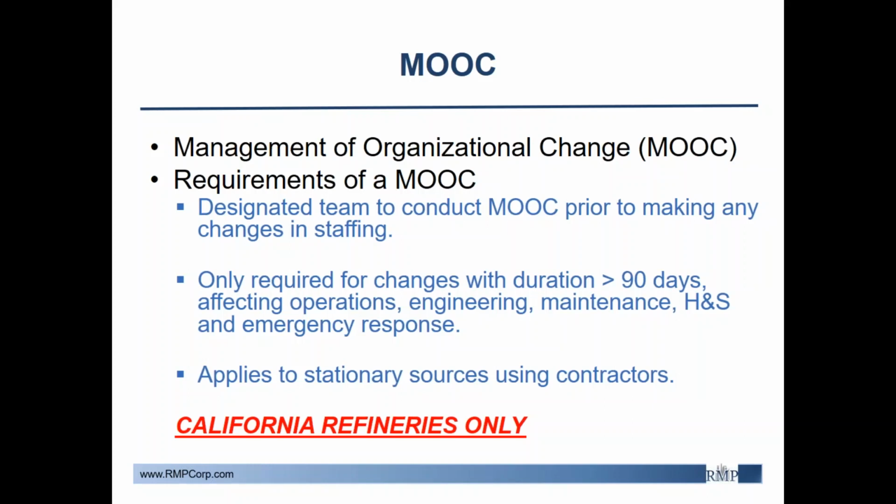The MOOC assessment is required only for changes with a duration exceeding 90 calendar days, affecting operations, engineering, maintenance, health and safety, and emergency response. This requirement shall also apply to stationary sources using contractors in permanent positions. This is something that's only being recommended for all facilities to do. However, it's being required for all California refineries.